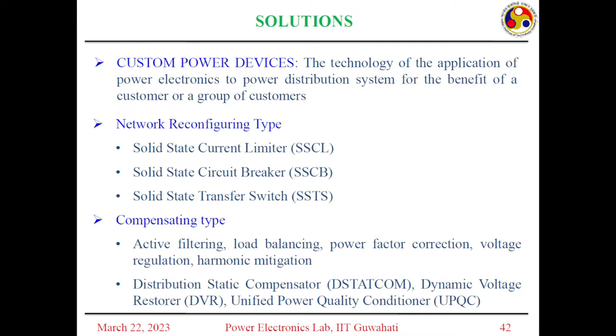So we have 2 major categories of these devices. One is the network reconfiguring type, another is the compensating type. The network reconfiguring types are the solid state current limiter, the solid state circuit breaker, and the solid state transfer switch. We also have the compensating type, with 3 well known devices: the distribution static compensator, the dynamic voltage restorer, and the unified power quality conditioner. These are the major compensating devices. By using these devices, we can solve the problems of harmonics, which is called active filtering, and load balancing, power factor correction, voltage regulation, and harmonic mitigation. All these problems can be solved by using these devices.